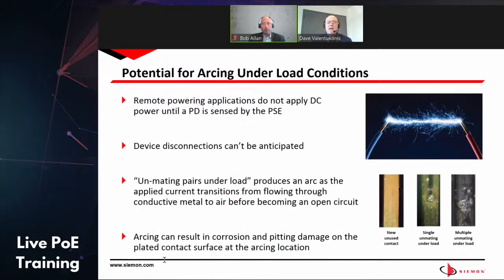Now, when we talk about connectivity, what really comes into play is that when you have a powered device, there's always a handshake. It's never delivering power from the PoE switch to the PoE device until it actually has a handshake. And once it has that handshake, it's going to operate as usual. So the only situation where you're worried about this arcing under load is if you disconnect a live port from the end device. And what are the implications to your structured cabling on that?